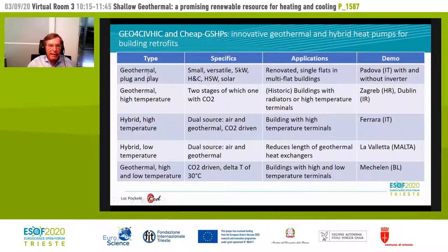Our partner Hyref from the Galetti Group and Galetti Belgium are developing 5 different types of geothermal heat pumps. The first one is aimed at being installed in single flats in multi-flat buildings. It's like a cupboard with everything ready to be connected immediately to the heating or cooling circuit, to the fan coils, or the radiant panel heatings, or even the ventil convectors. We are testing that with 2 pumps to see the effect of working with or without an inverter on the compressor of the heat pump. We can also attach solar panels. This is a very nice solution in renovated building flats, where we put a loop of ground heat exchangers and supply the geothermal heat pump through the building to the heat pump in the different apartments.